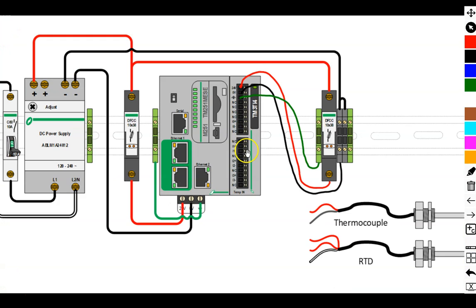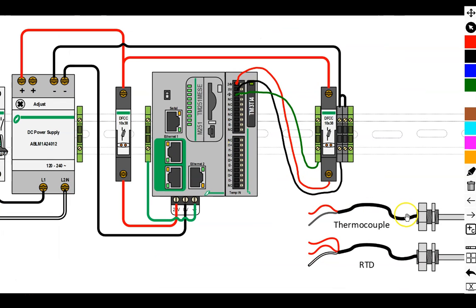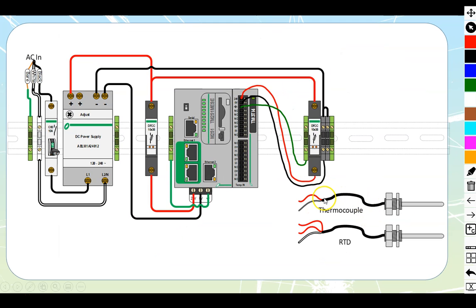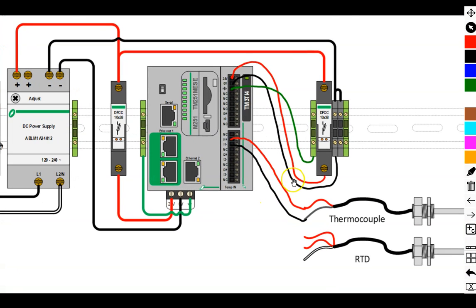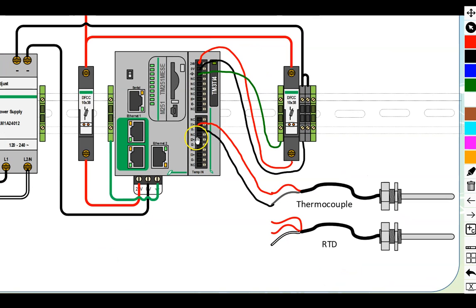We're going to take that thermocouple up to this one right over here, I1, positive and negative. So my thermocouple over here is going to be a two-wire device. I did not put a type to it because it wouldn't really matter which type. And we are going to just connect our positive onto our red and our negative onto our black. So we'll do that over here. Positive comes into the I1 positive. Negative is going to come into the I1 negative, like that. And we will once more just zoom in so we can read those terminals off of here. Positive and negative running into those two there. Perfect.